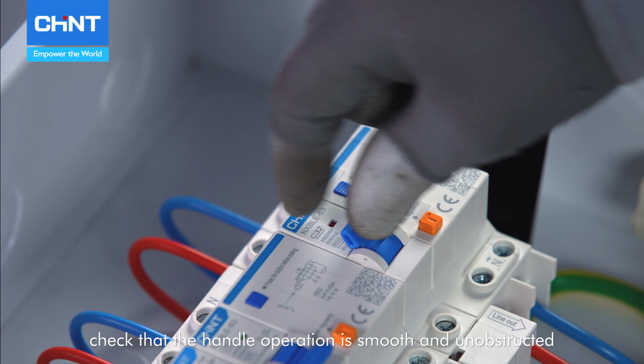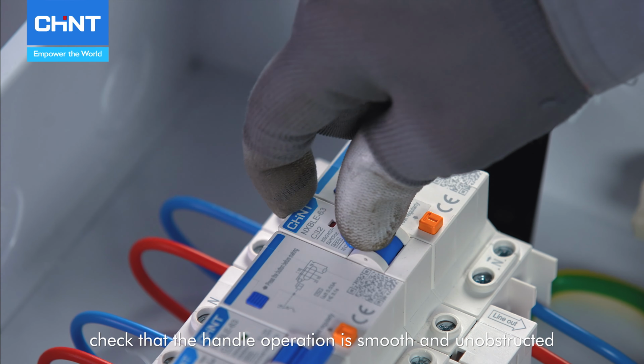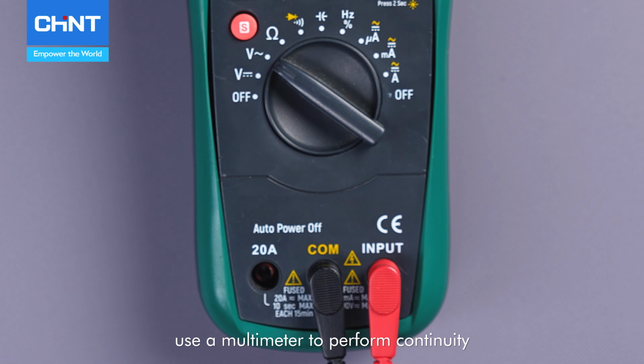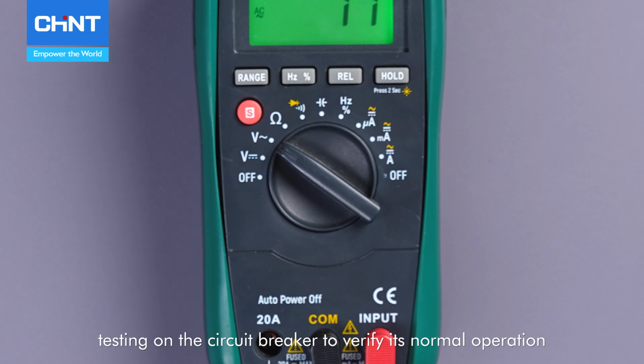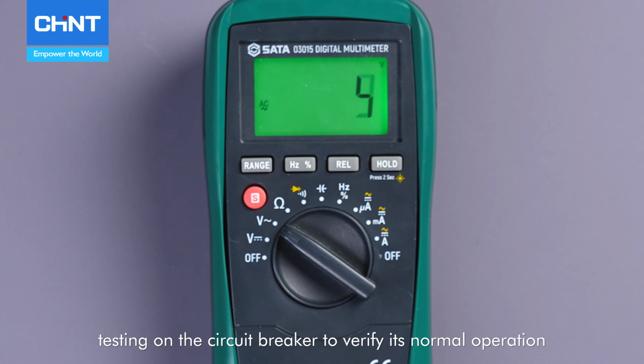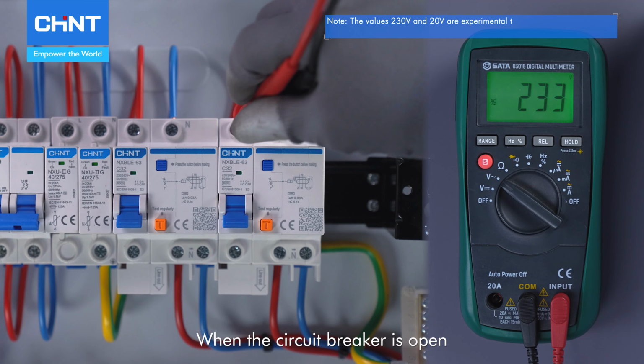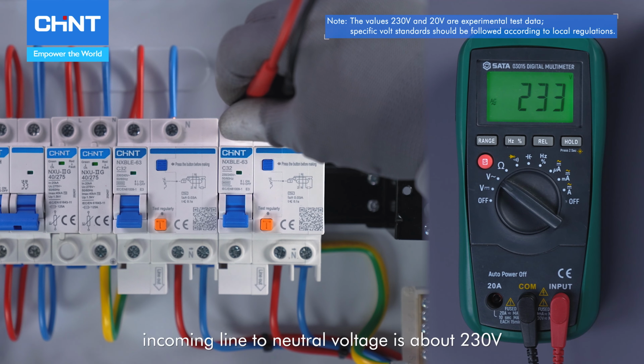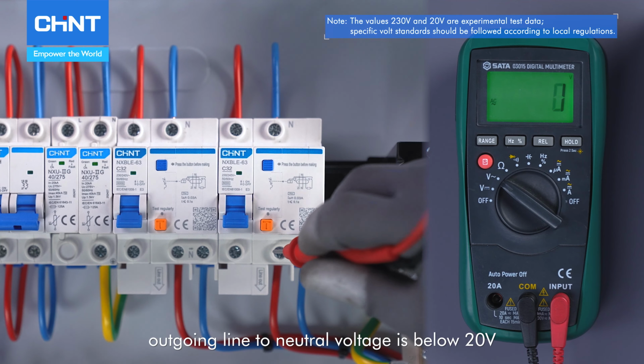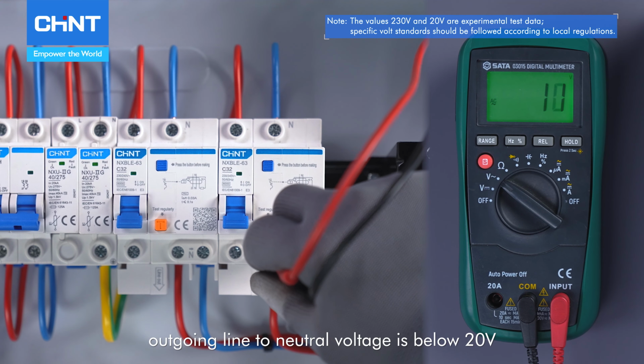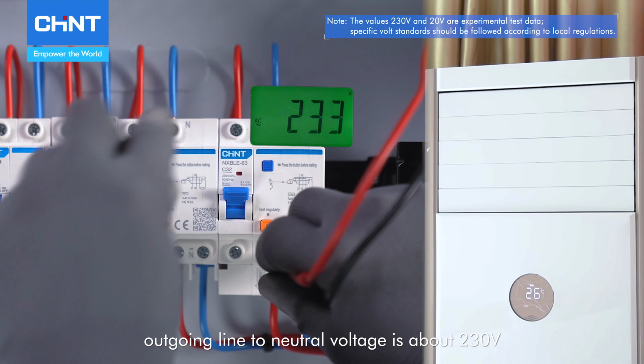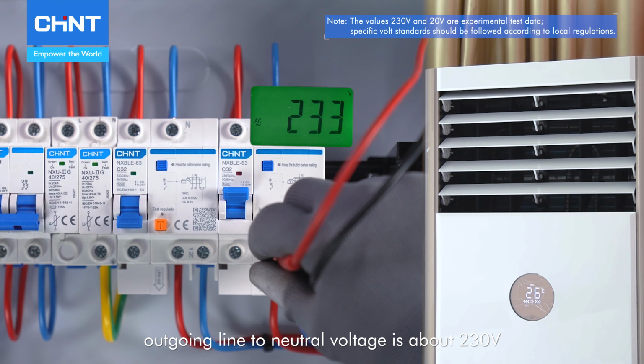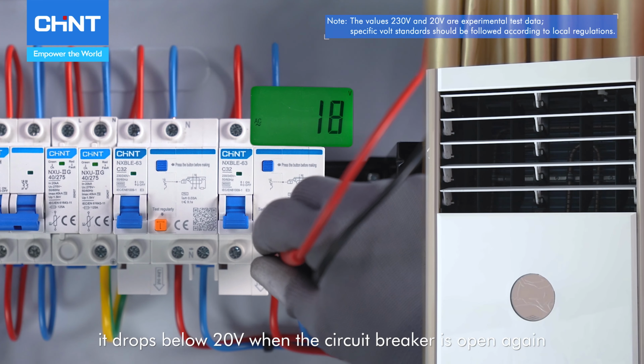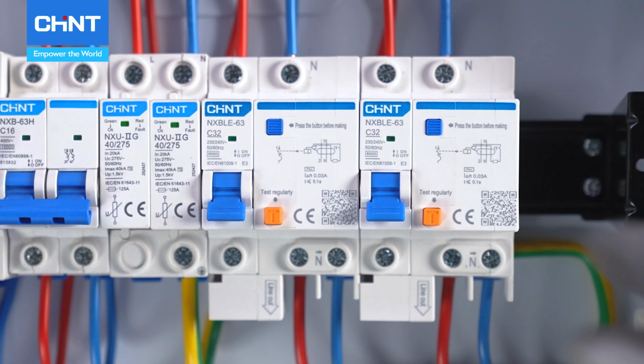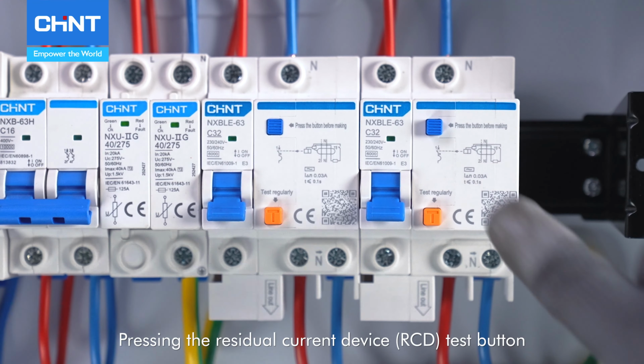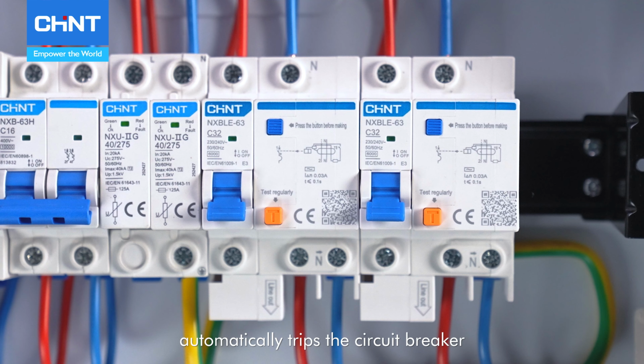Before powering up, check that the handle operation is smooth and unobstructed. After powering on, use a multimeter to perform continuity testing on the circuit breaker to verify its normal operation. When the circuit breaker is open, incoming line to neutral voltage is about 230 volts, outgoing line to neutral voltage is below 20 volts. When closed, outgoing line to neutral voltage is about 230 volts, and it drops below 20 volts when the circuit breaker is open again. Pressing the residual current device test button automatically trips the circuit breaker.